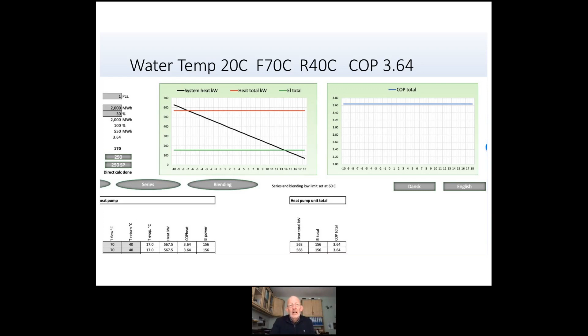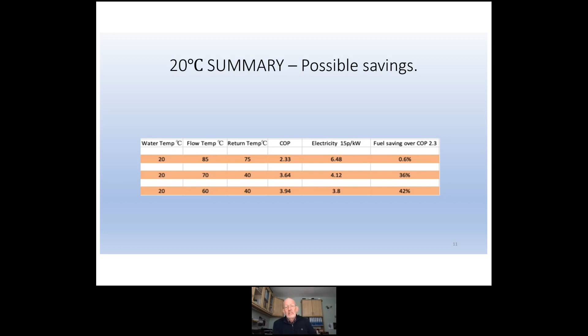This is another table showing the source water at 20 degrees C and the flow and return temperatures, and here we can increase it to potentially 42% better than our base numbers. And if we join them all together, combine the tables, we can see that 20 degree C water is slightly better than 10 degrees, but the operating temperatures are shown to be so much more influential on the COP numbers.